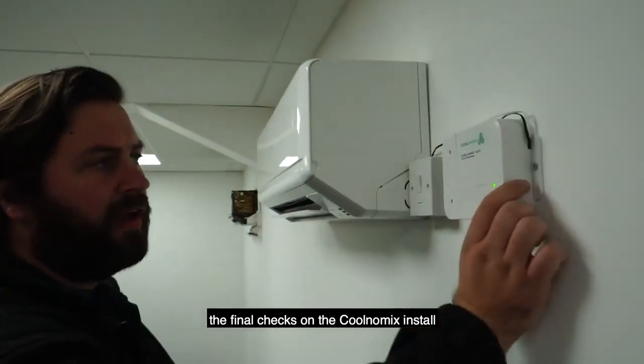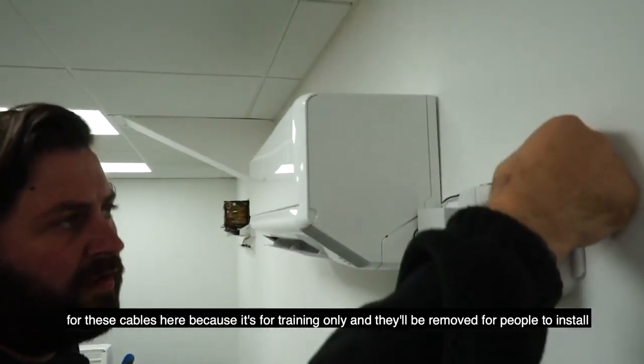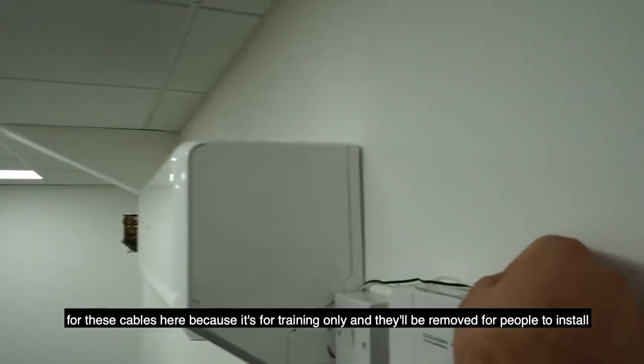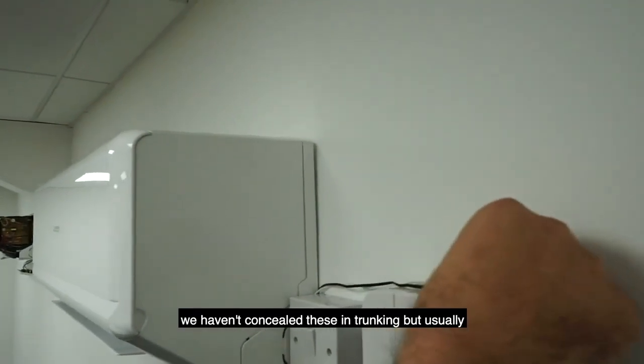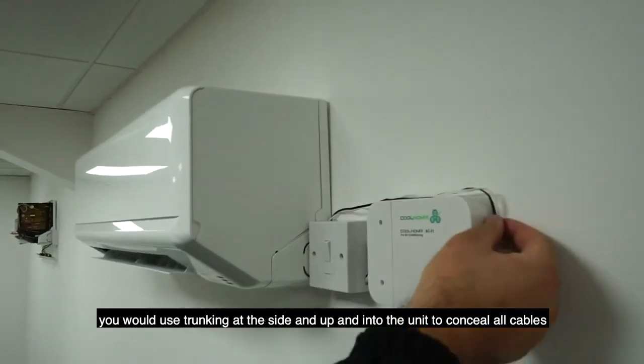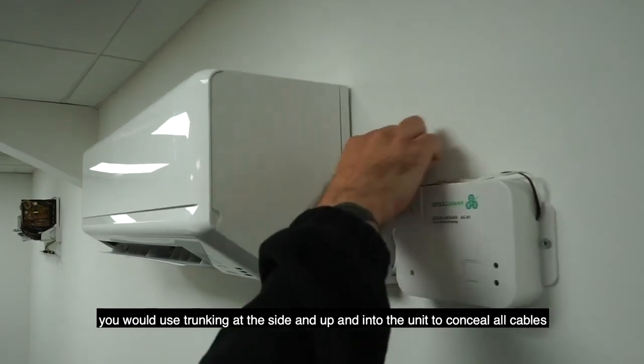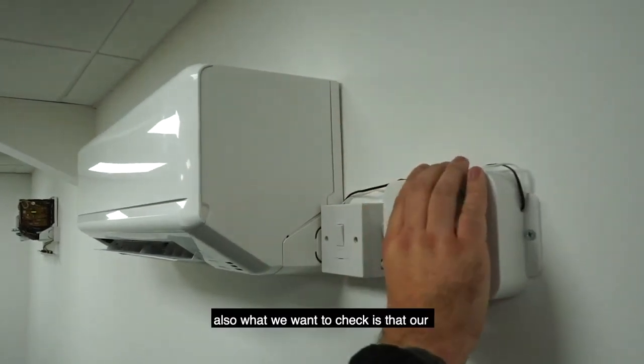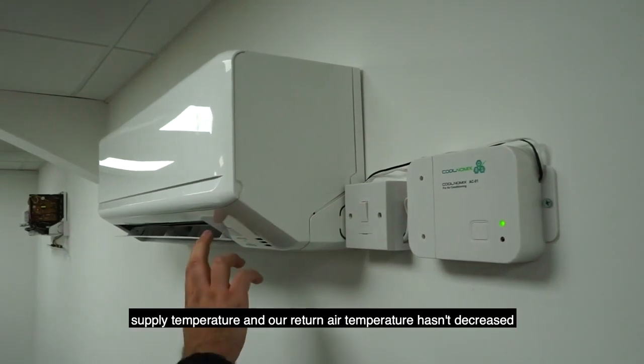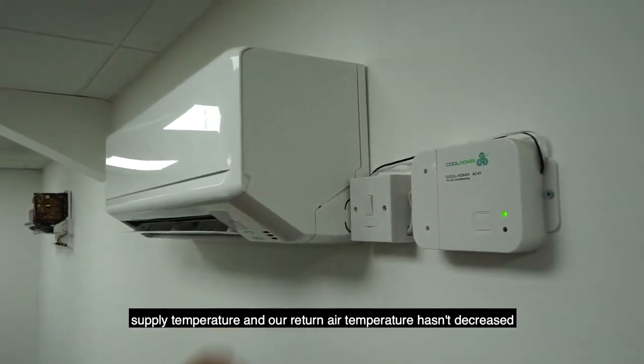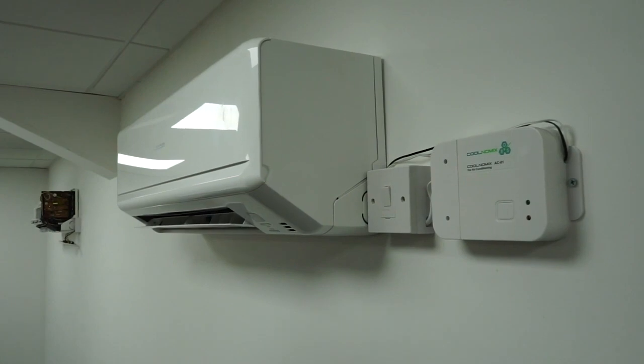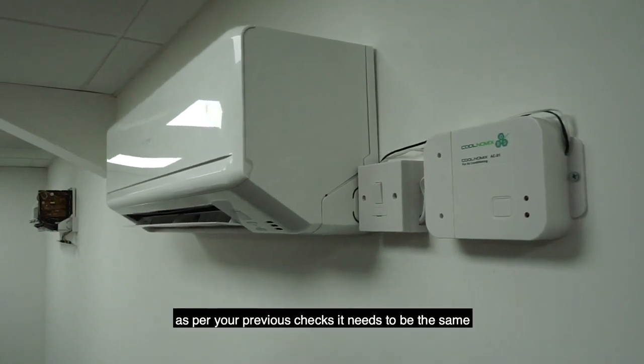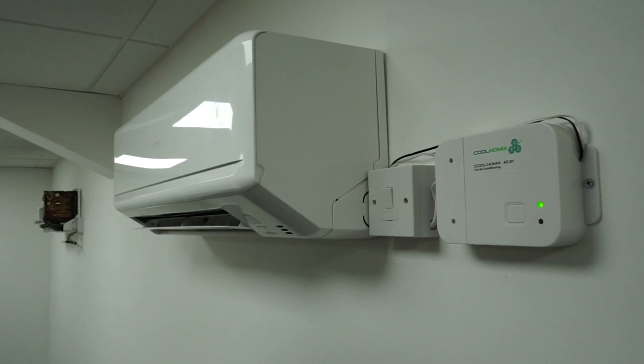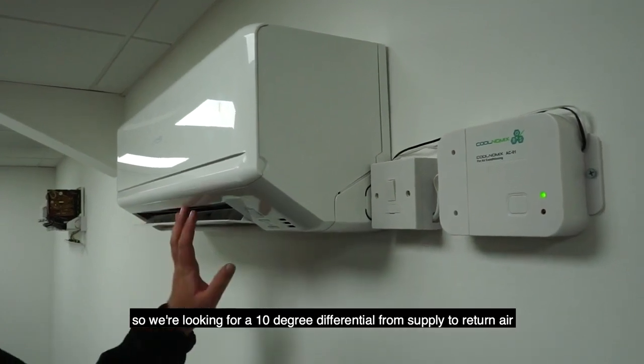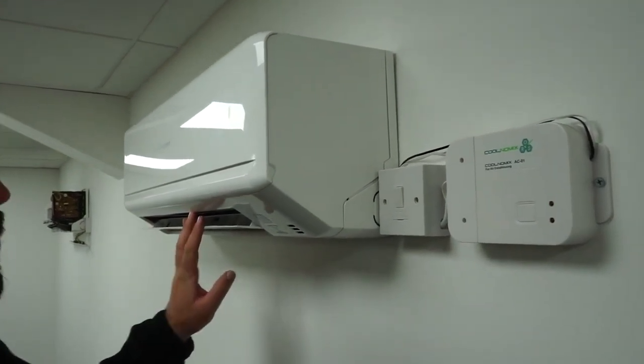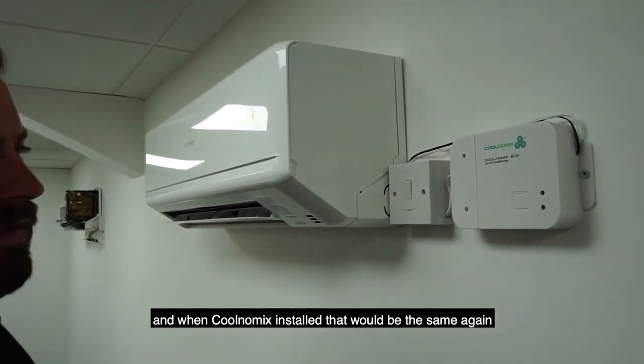So final checks on the Coolnomix install. With these cables here, because it's for training only and they'll be removed for different people to install, we haven't concealed these in trunking, but usually you would use trunking at the side and up and into the unit to conceal all cables. Also, what we want to check is that our supply temperature and our return air temperature hasn't decreased as per your previous checks. It needs to be the same. So we're looking for a 10-degree differential from supply to return air, and when Coolnomix is installed, that will be the same again.